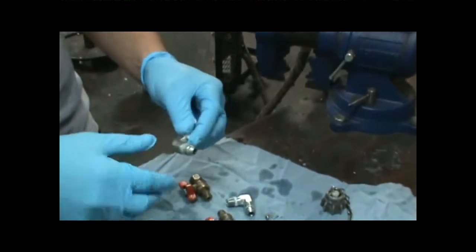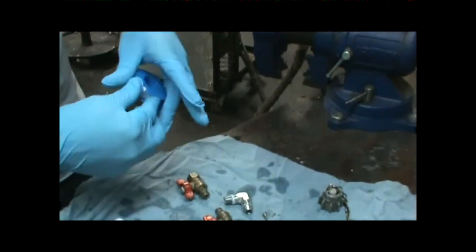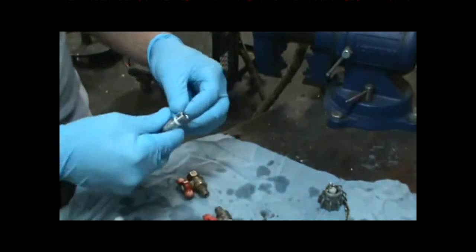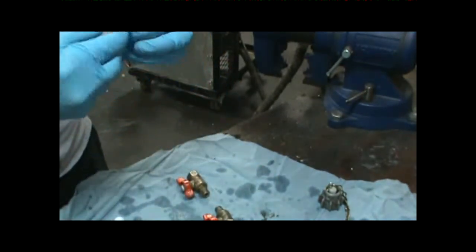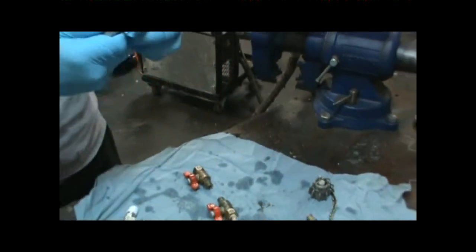This side, do not put Teflon on. It is the compression fitting for the hose. Just the pipe threads is what you want to apply the Teflon to to make sure you don't have any leaks when you reassemble it.